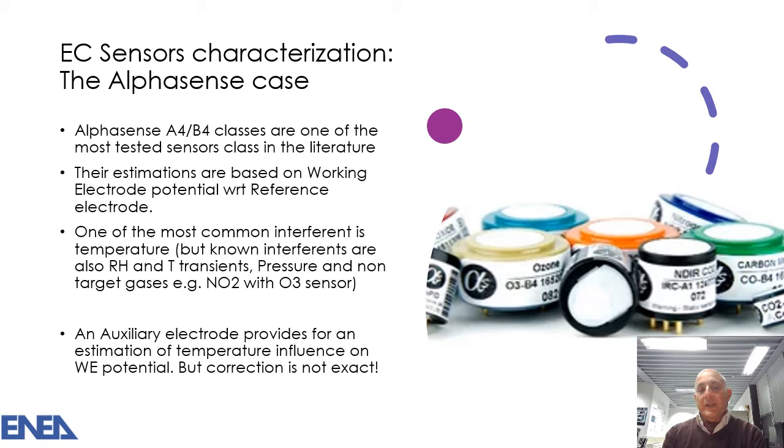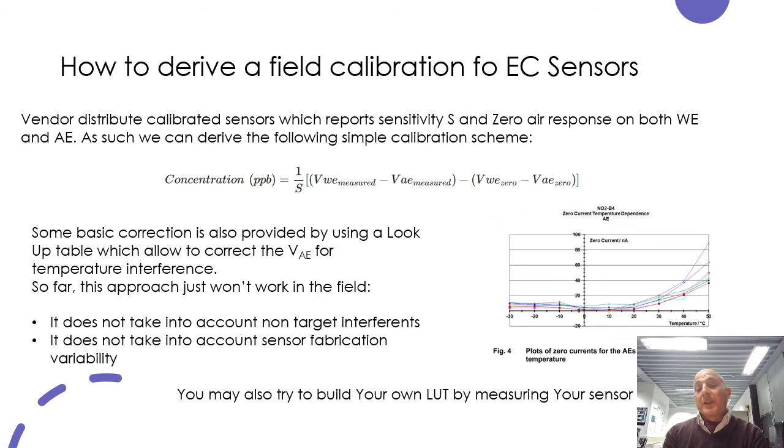However, this correction is not exact, so we have to improve the correction with an ad hoc calibration. Unfortunately, the fabrication variance of this kind of electrochemical sensors forces us to derive an ad hoc calibration for each of the sensors, at least in our basic approach. But the vendor also distributes calibrated sensors, which report the sensitivity and the zero error response on both working electrode and auxiliary electrode.